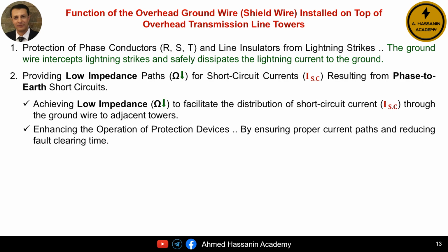Therefore, we understand from this that the presence or importance of the shield wire or earth wire or ground wire is that it provides a low impedance path for earth fault currents and lightning currents. The second point is that it helps in distributing the earth fault currents and the currents resulting from lightning strikes over the adjacent towers. The third point, according to what we have said, is that all of this results in better operation and higher efficiency of the protection devices.